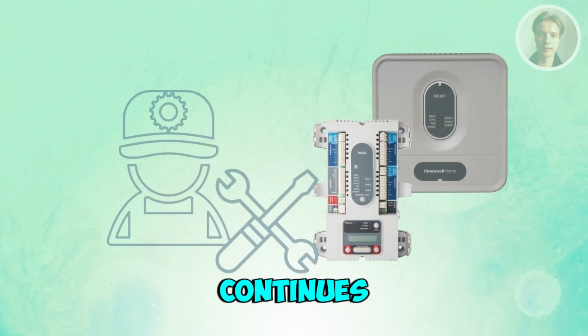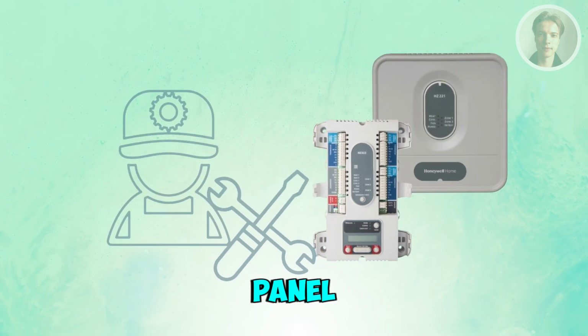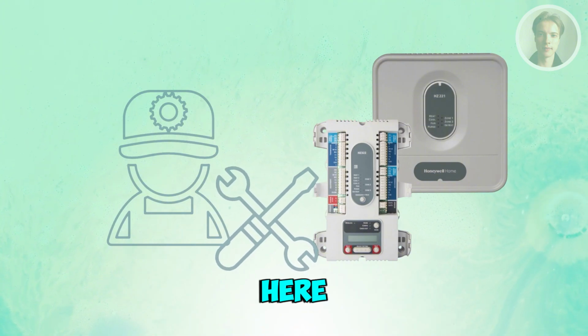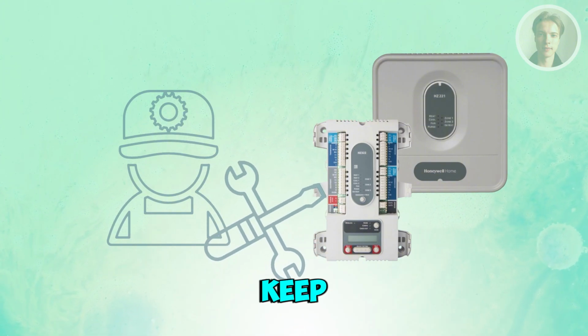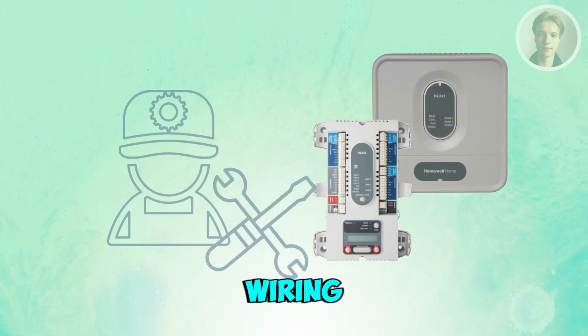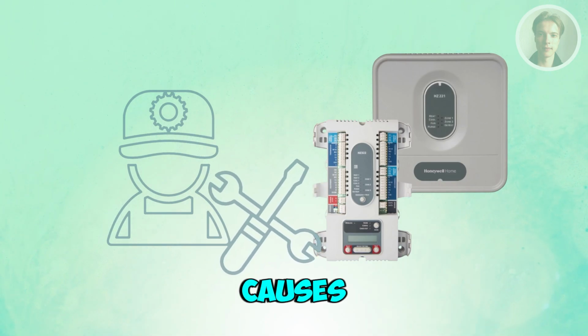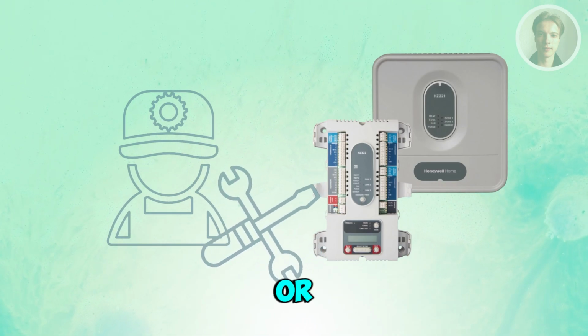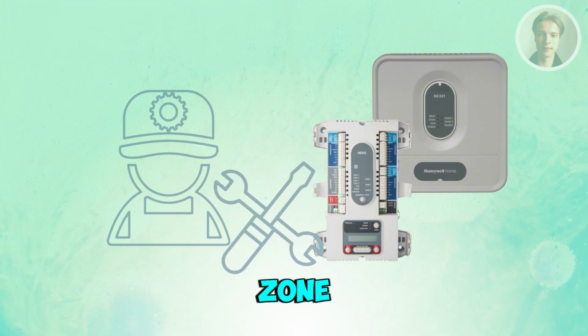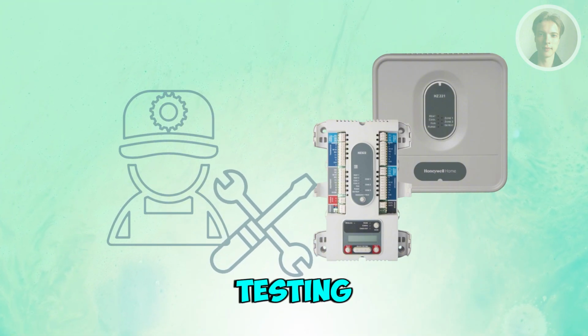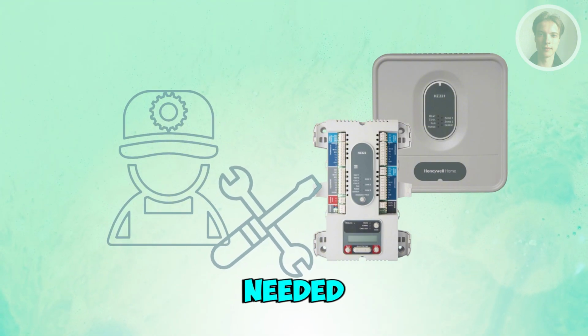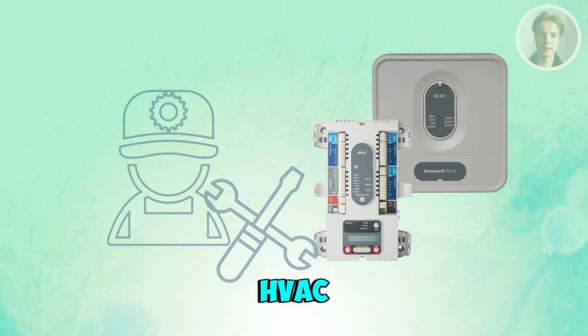Now, if the blinking continues, a damper motor or panel board is likely failing here. So basically, if the lights keep cycling even after the reset and the wiring looks good, the most common causes are a failed zone damper motor, a weak transformer, or a failing TrueZone control board. Now, at this stage, testing the voltage and damper movement is needed, which is best handled by an HVAC technician.